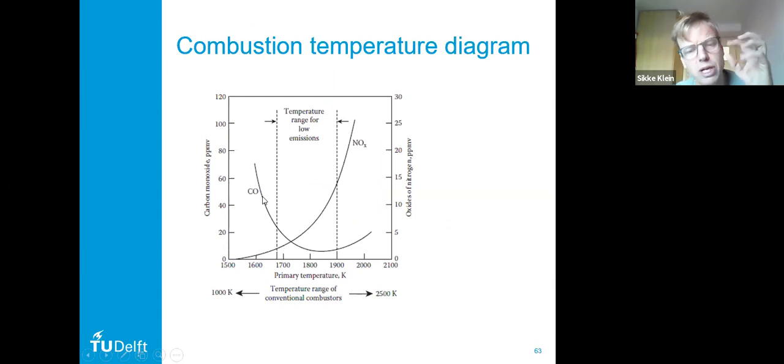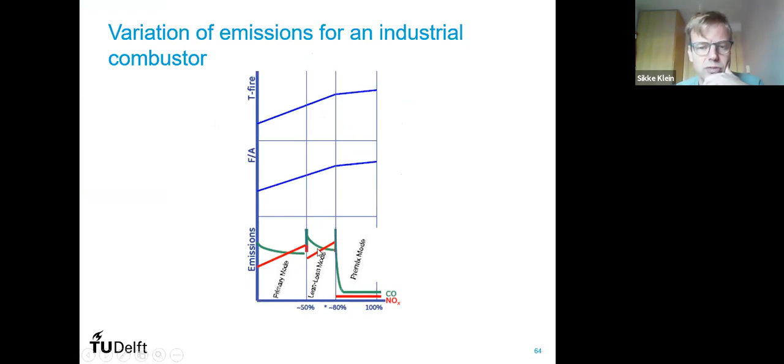So you miss the temperature in your combustion triangle. And therefore, you have to go to a kind of primary that's not fully premixed, and the DLN is a combination of premixed and non-premixed. So you really see here that this is the challenge in this situation. In this case, you have low NOx and low CO. You see here CO is increasing, and then you switch to these modes. That's the challenge with premixed combustion. You only have a small operational range. There are a number of tricks to deal with that, like switching off burners and things like that. But that's really the challenge with premixed combustion: how to operate over a large operational range.